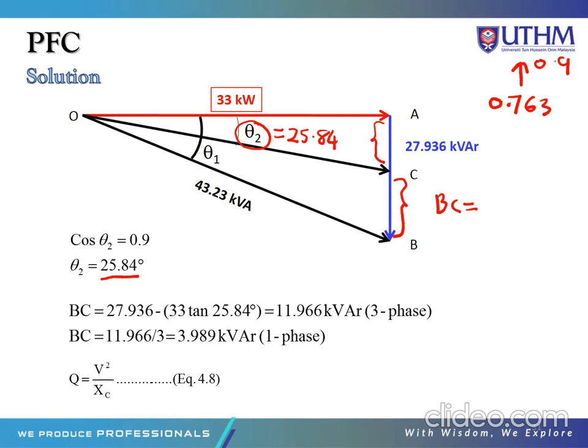We have to subtract AC from AB. So BC is the kVAR that will be installed to the system to improve the power factor from 0.763 to 0.9. This is the AB, which is already given, the Q for the existing. And to get the AC, we use this formula, P tangent theta 2. So we get the BC equal to this value.